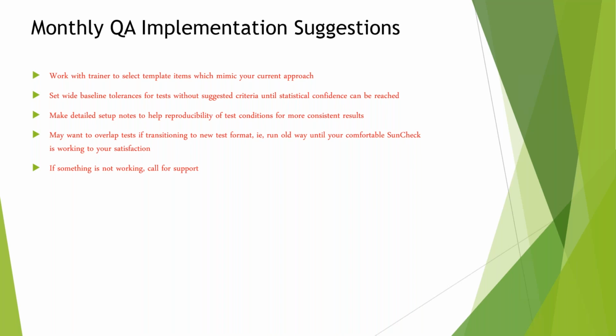So in retrospect, if we had to do it again, we would suggest working with the trainer to select template items that mimic your current approach. Set wide baseline tolerances for tests without suggested criteria until statistical confidence can be reached. Make detailed setup notes to help reproducibility of test conditions for more consistent results. As you know, you're only performing tests monthly, and it's hard to remember sometimes what you did last month unless you jot it down.